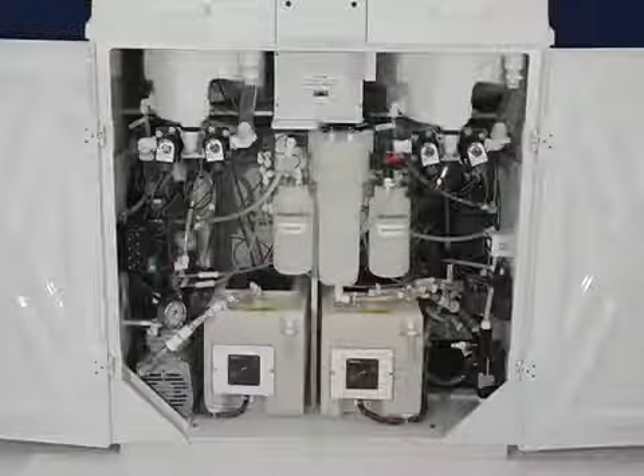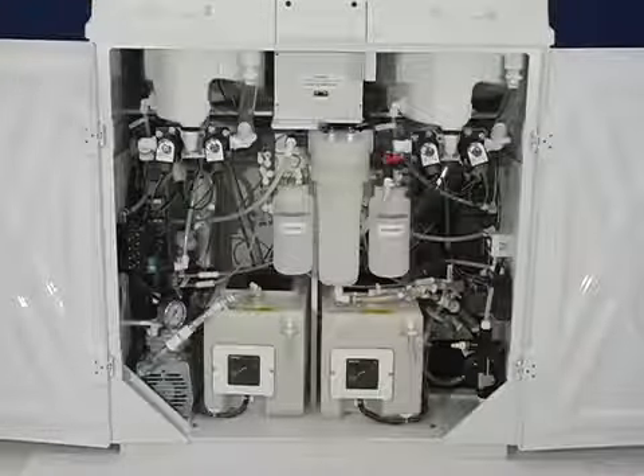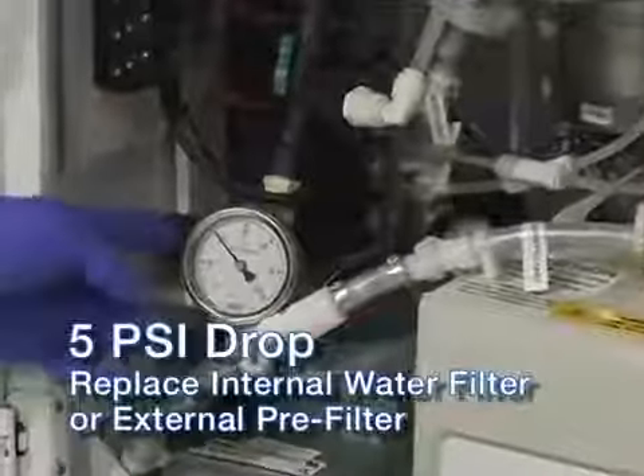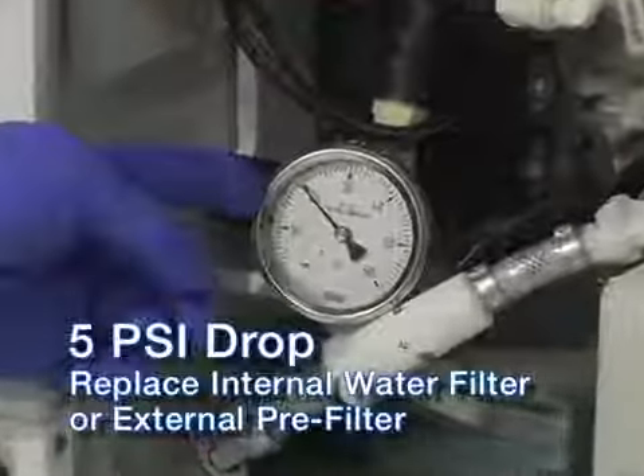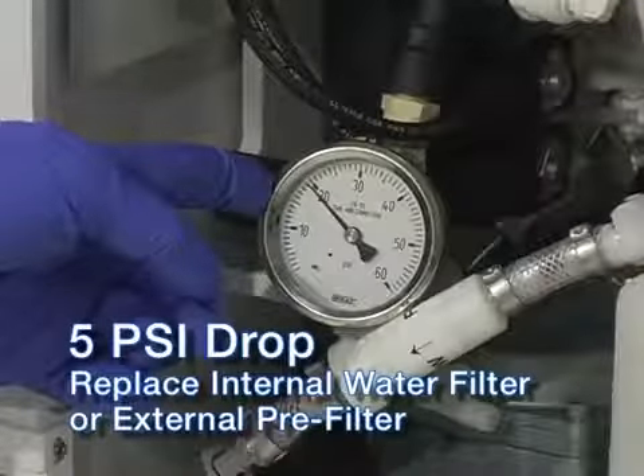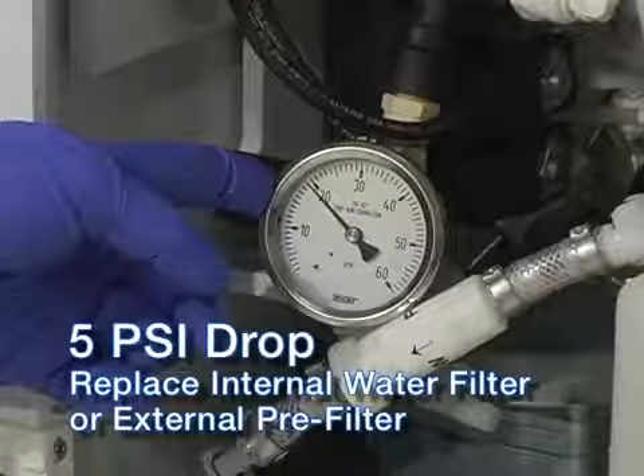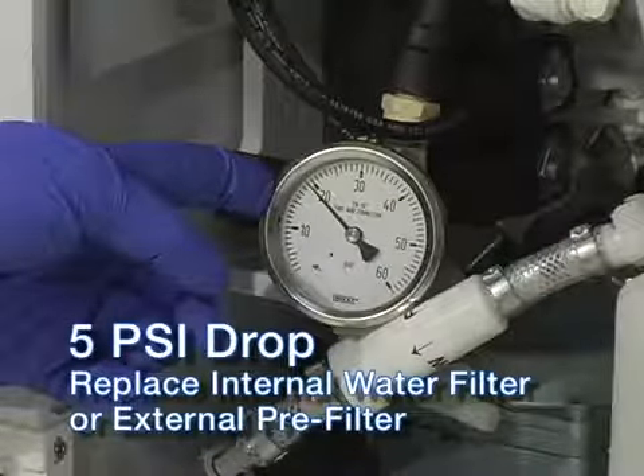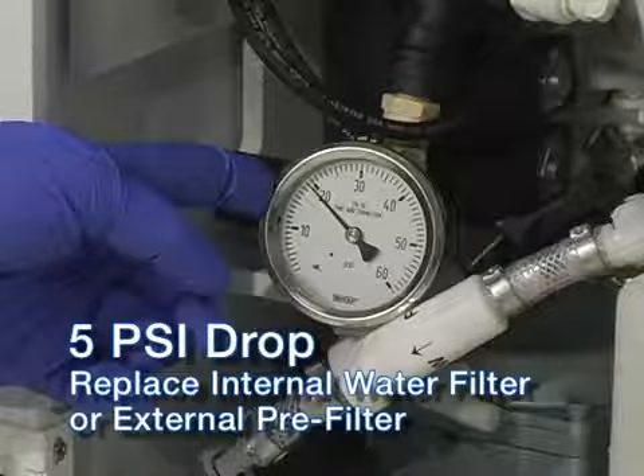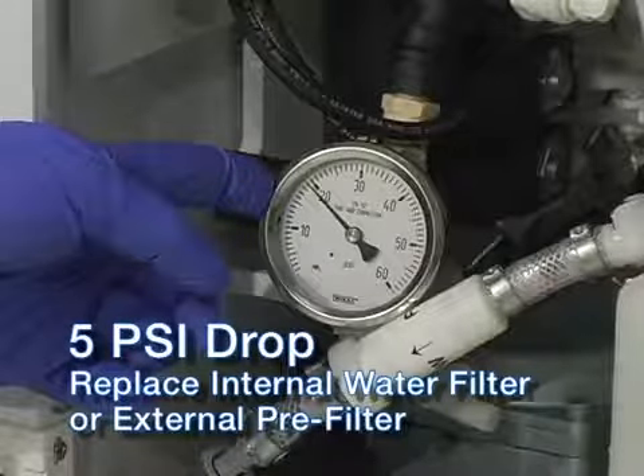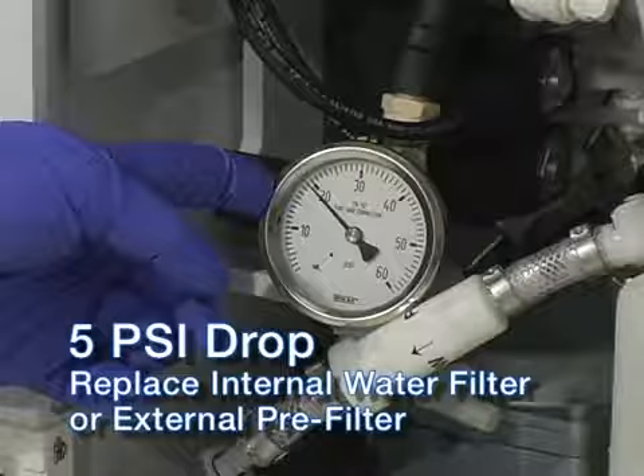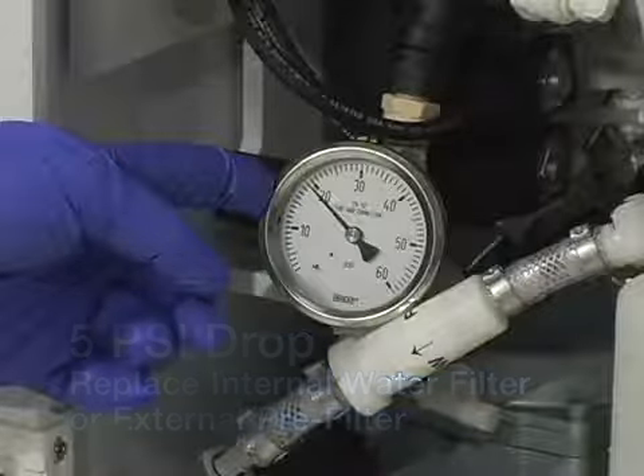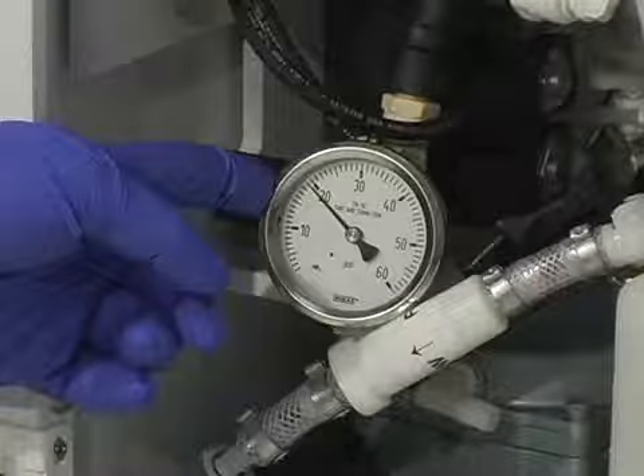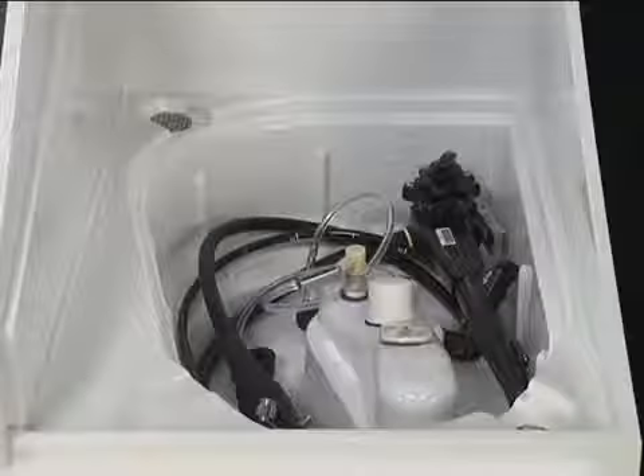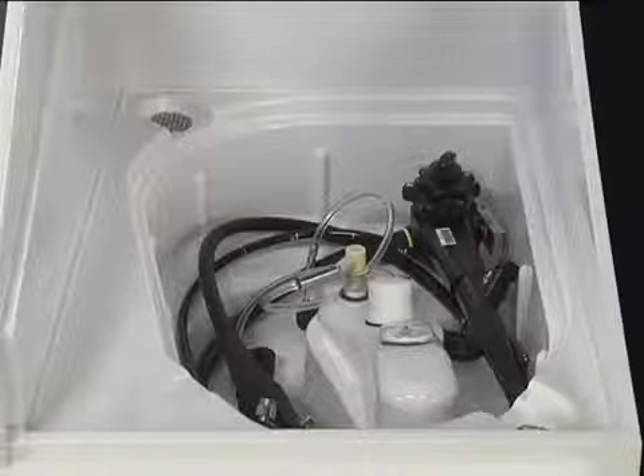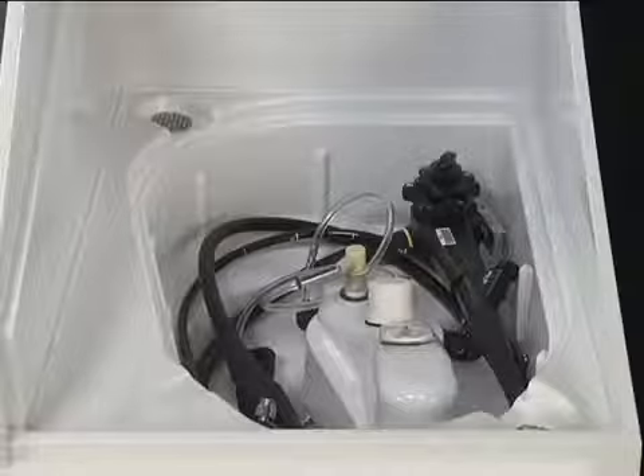When you are disinfecting the first endoscope of the day, check the water pressure while the DSD-201 is in a flush cycle. If the pressure has dropped 5 or more psi from the target setting of 20 psi, it is a sign that either the pre-filter or the internal 0.2 micron filter is saturated. Replace the appropriate filter as soon as the endoscope disinfection cycle is completed. Changing of these filters will be covered later in this video. In the next section, we will demonstrate the steps necessary to disinfect an endoscope in the DSD-201.